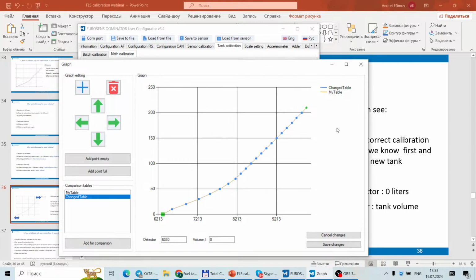We need to know empty and full sensor values, the internal detector values for empty and full tank. So we need to cut the sensor and calibrate it in the tube for the second vehicle. And we will know these detector values for the second vehicle. After that, we can choose this point. Let's imagine our new value is 6400, and we choose this point and then move the plot to our new value. Same with the endpoint. Let's imagine it would be 10,000. So we move this point as well.